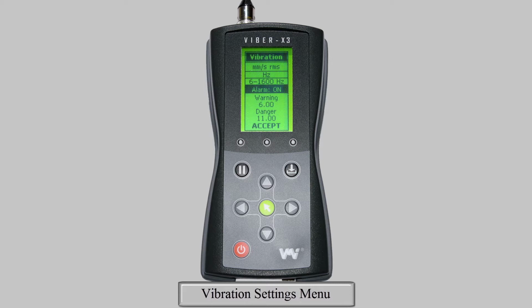The last area of this submenu is to configure your alarm levels. You can change the values of the warning and danger levels or turn them off, if not required. You do this by highlighting the alarm function and using the left and right arrows to change between on and off. To change the values of the warning and danger levels, we do the same as for the transducer sensitivity setting that was shown earlier. Highlight the value and then press either the left or right arrows.